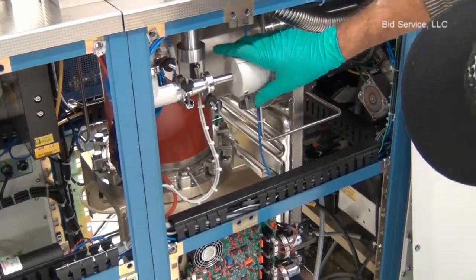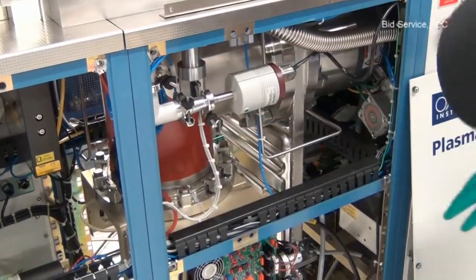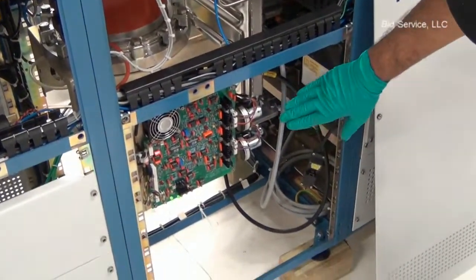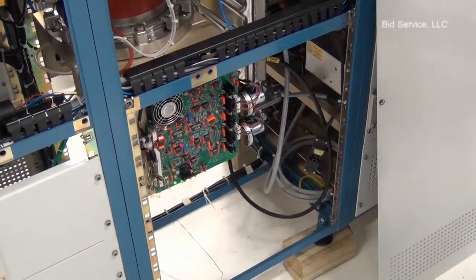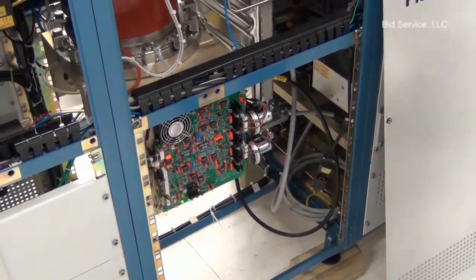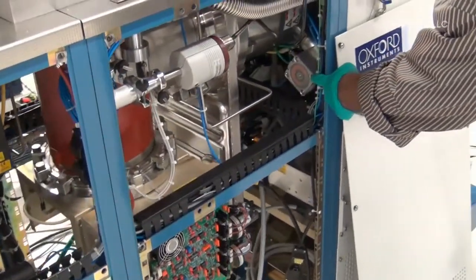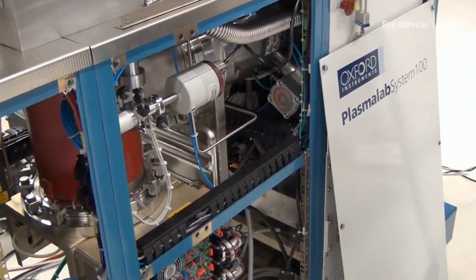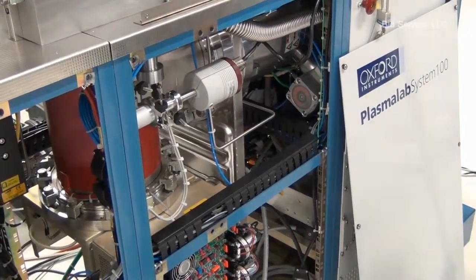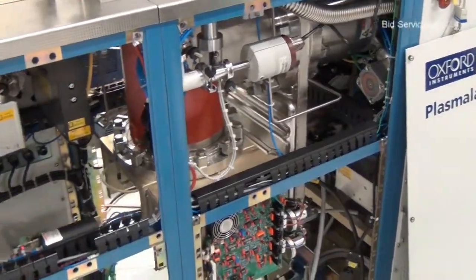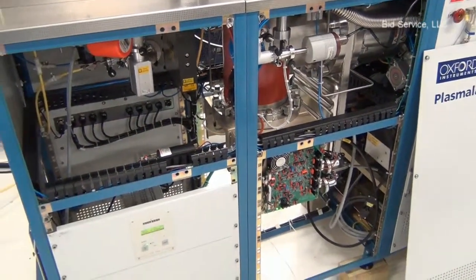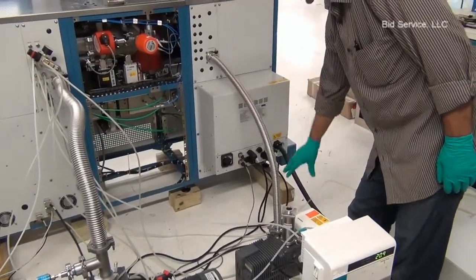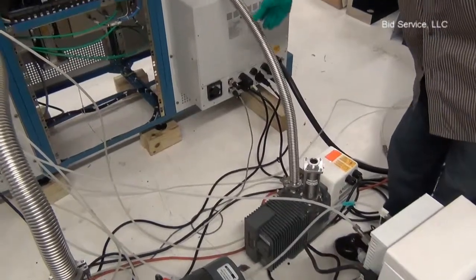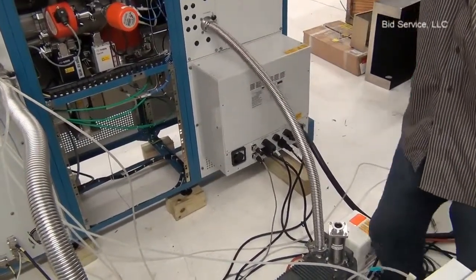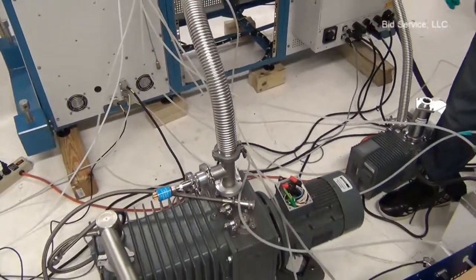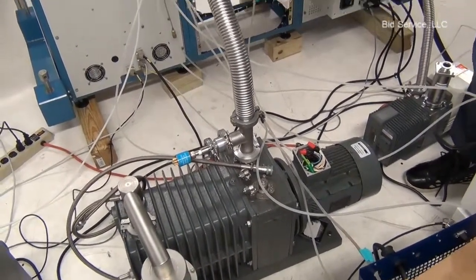This is the baratron sensor for chamber process pressure monitoring, and this is the matching network controller. The main turbo valve. This is the foreline valve for the main turbo pump, which is also heated. Here's the small mechanical pump for the load lock chamber. And this is the main pump for the main chamber and main turbo pump.